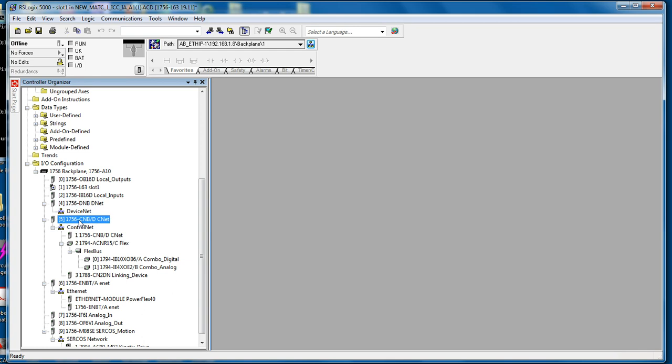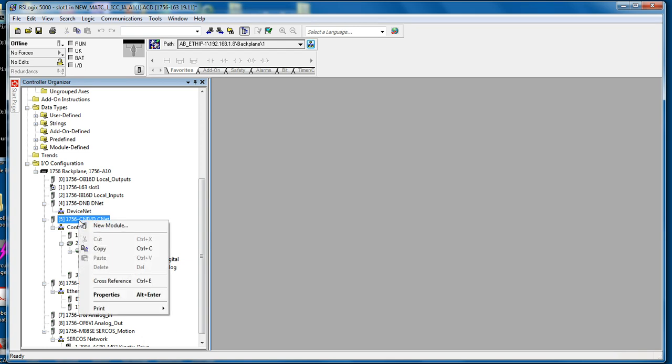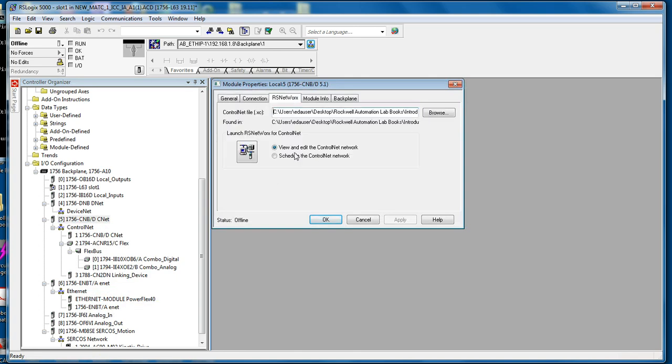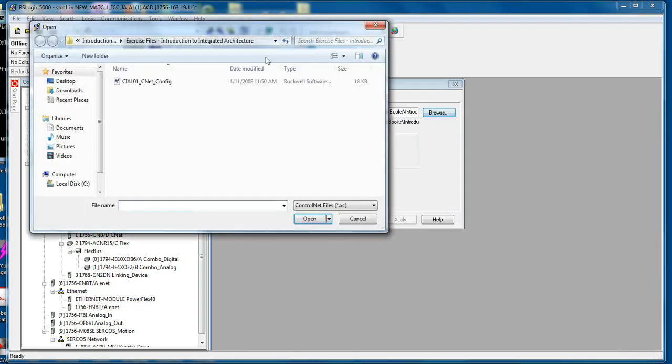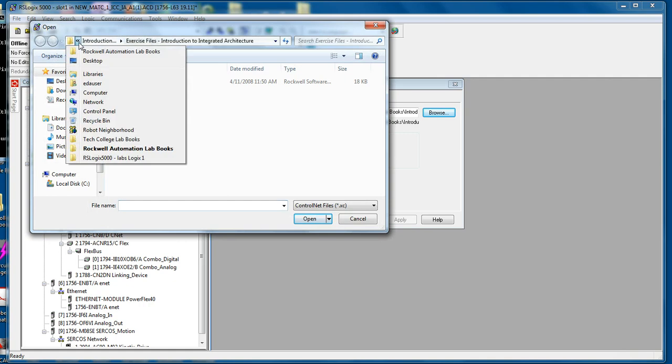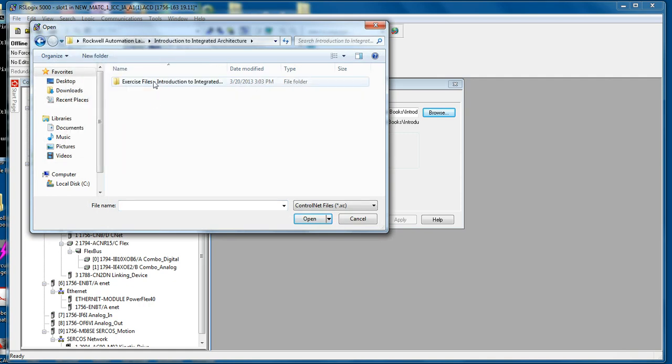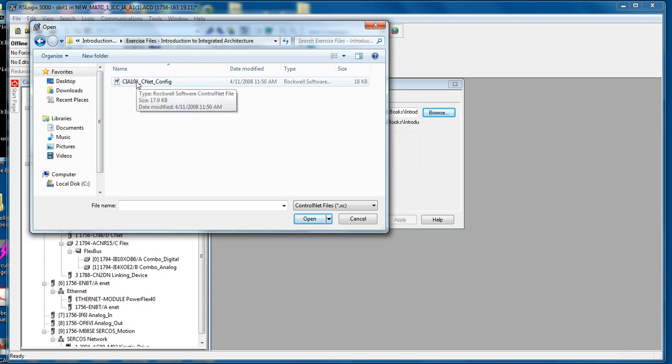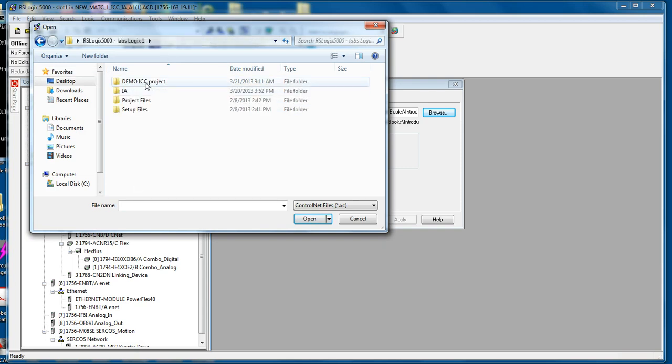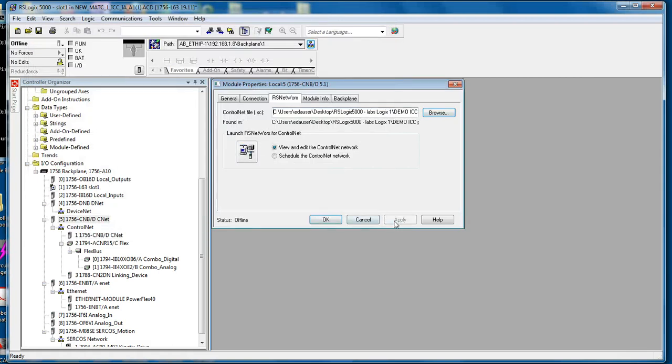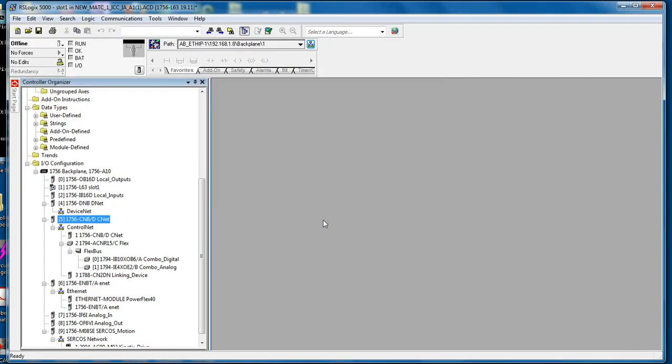Then we go into slot number 5, the control net card, same thing. Highlight it, right click, properties, go to the RSNetWorx tab, click browse, find the file that we want to load. Here you see only one file is available since it's the only control net configuration file. Click apply. Check the schedule control net radio button. Click OK.